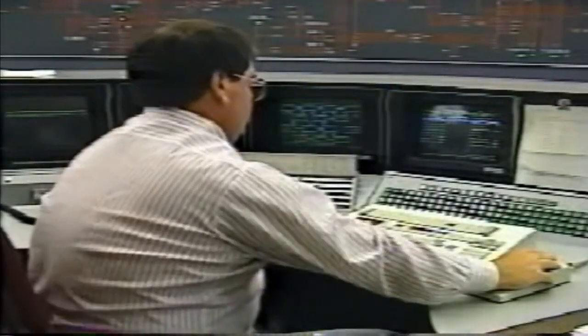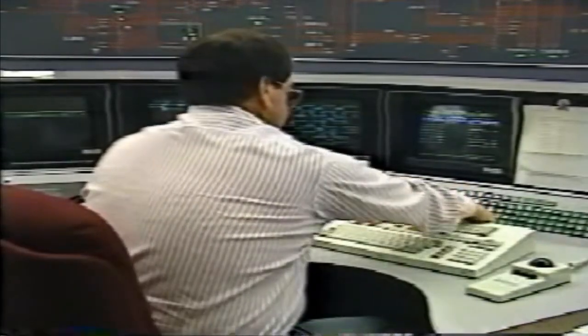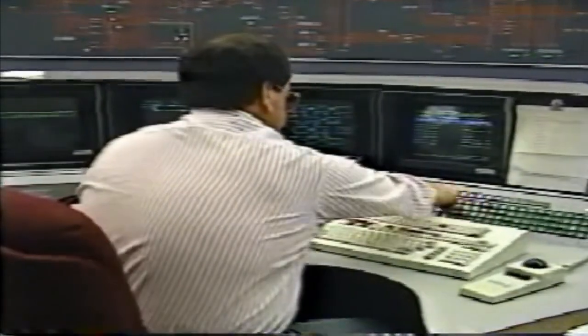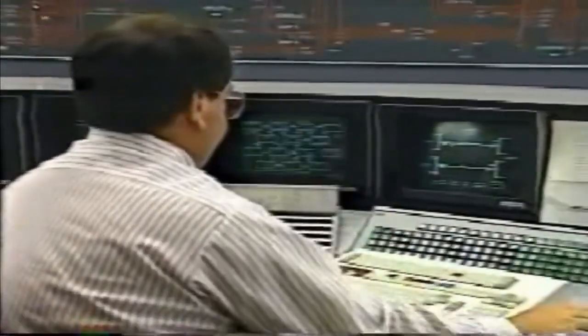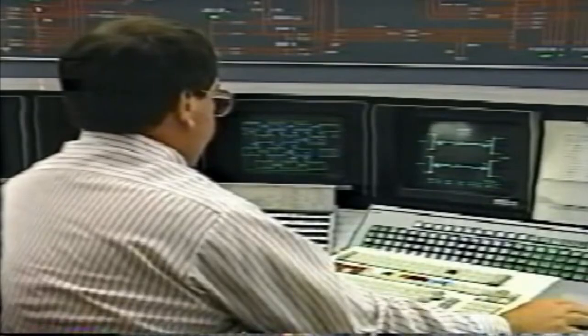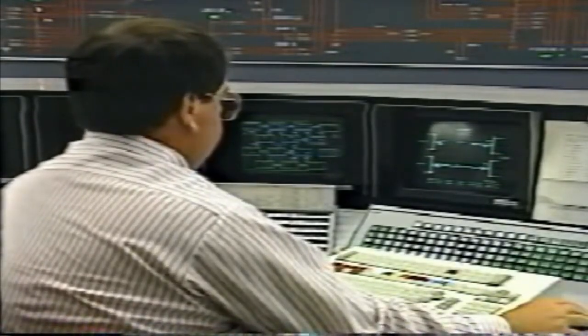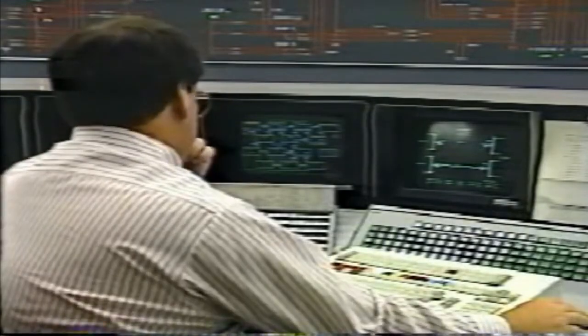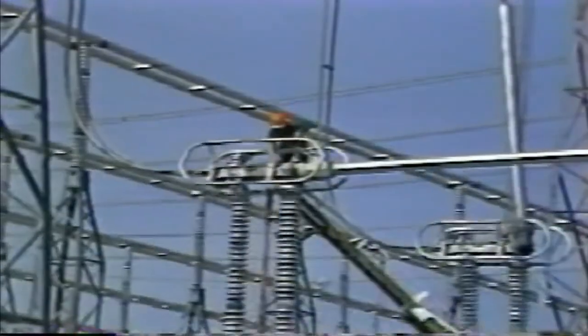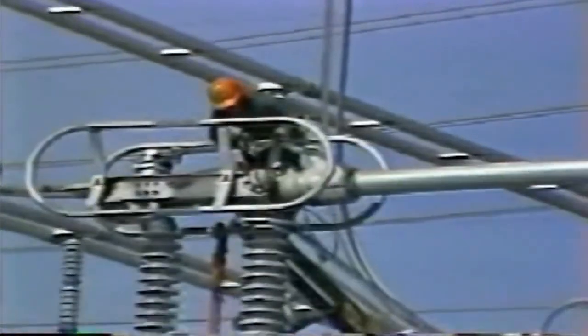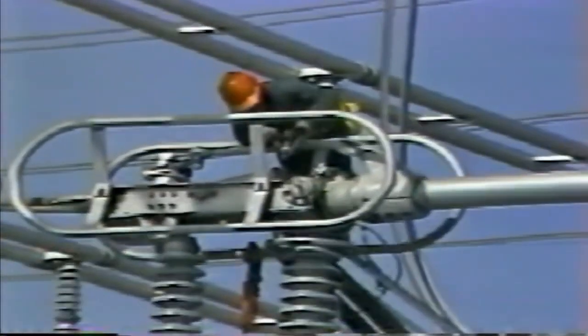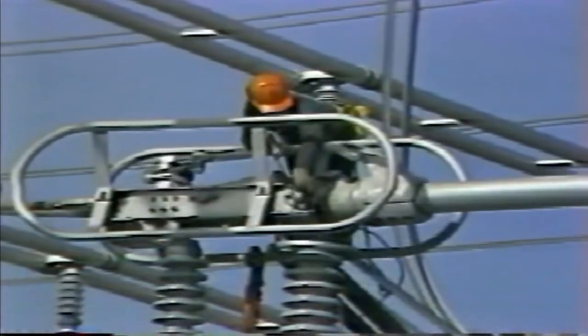So before permitting any requested outage to take place, this information enables the system operator to rearrange load flows around the system and perhaps modify the interchange commitment. All of this highlights the necessity for good planning and advance notice of any outage requirements. Even with a planned outage in progress, the system is still considered to be operating normally, as the system operator is able to arrange the system to accommodate this. Indeed, if you think about it, I'm sure you'll agree that on your own power system, there's always at least one major item of equipment out of service at any given time.